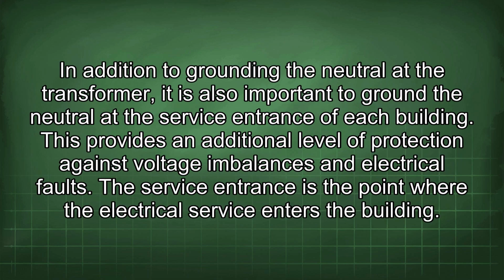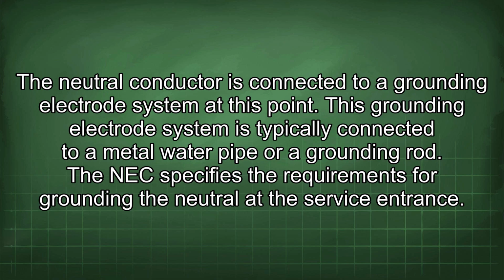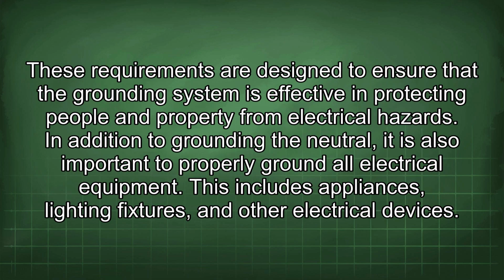In addition to grounding the neutral at the transformer, it is also important to ground the neutral at the service entrance of each building. This provides an additional level of protection against voltage imbalances and electrical faults. The service entrance is the point where the electrical service enters the building. The neutral conductor is connected to a grounding electrode system at this point. This grounding electrode system is typically connected to a metal water pipe or a grounding rod. The NEC specifies the requirements for grounding the neutral at the service entrance. These requirements are designed to ensure that the grounding system is effective in protecting people and property from electrical hazards.